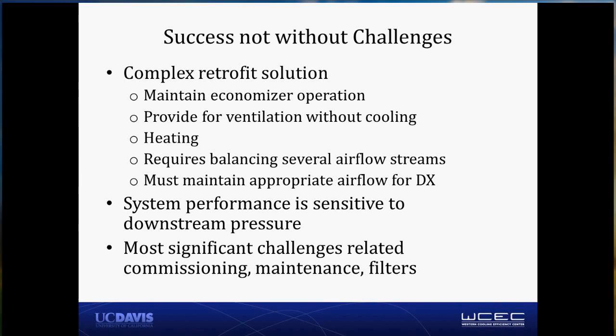Controls contractors should be able to do this, but it does require a different type of control strategy that makes a smart decision about when the whole building should run in economizer mode, when it should run in indirect evaporative cooling, and to make sure that it's always providing for enough ventilation, even during those periods in time when you don't need cooling, and in fact when you need heating. As I said before, the system performance for this equipment is sensitive to downstream pressure. That's a biggie. We've seen a couple of different applications that have had that trouble. Ours included. In fact, on one of the units, our control system failed to maintain appropriate downstream pressure, and performance on that one piece of equipment suffered significantly for it.